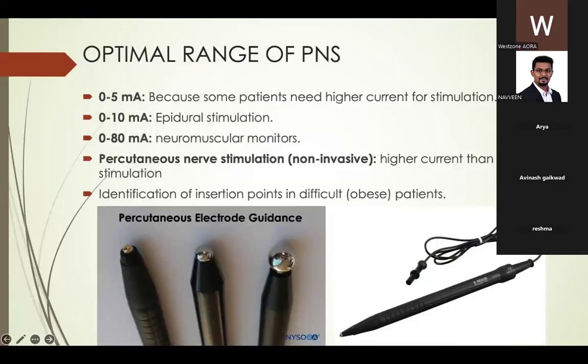So the optimal range of PNS is 0 to 5 milliamperes, which is used for peripheral nerve blocks, and 0 to 10 milliamperes is used for epidural stimulation, and 0 to 80 milliamperes is used for neuromuscular monitoring. There is also percutaneous nerve stimulation, which is a non-invasive technique that requires higher current than invasive stimulation, where the tip is placed over the skin. This helps to map the nerve in patients who are obese.